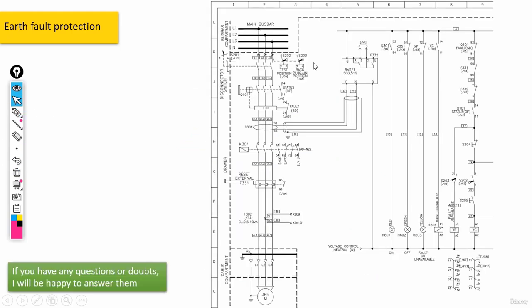I'm going to show you a real diagram regarding this whole concept. Okay, we have this diagram for a real control circuit. Up here, we have the three phases entering our electrical panel. Then here we got this manual switch. After that, we have this MCCB breaker. And then the transformer, the CBCT transformer. And well, obviously the transformer is being connected to the earth fault relay here. And well, there's this contactor here that we would use for turning on the motor, the three-phase motor.